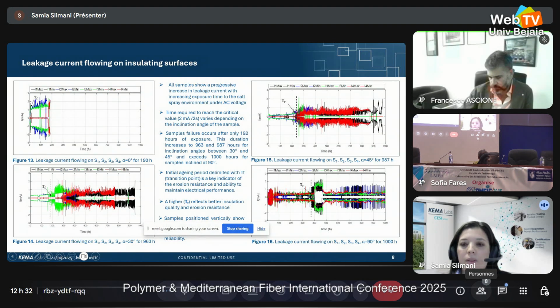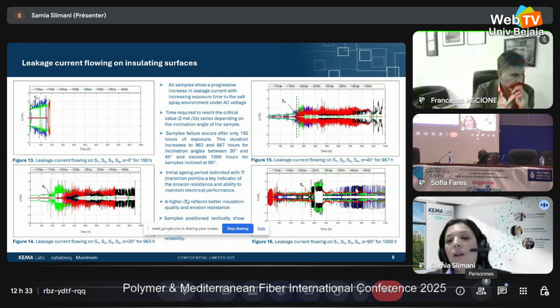Here the current starts to rise quickly and to reach big values of leakage currents. The third phase is the final aging phase. It's when the current reaches the criterion, which is 2 milliamp during 2 seconds, and after that the voltage switches off, and the test is failed.